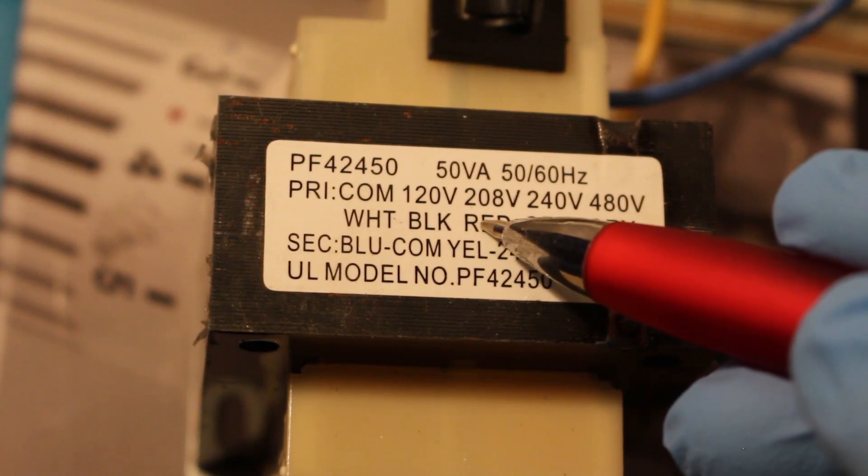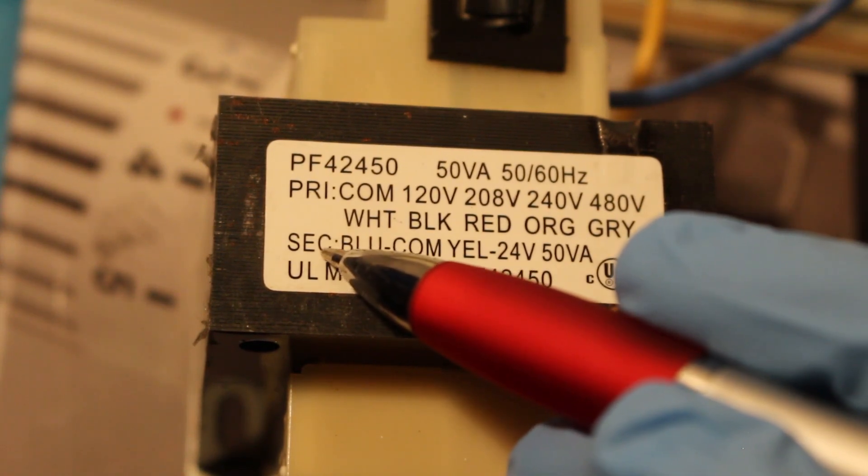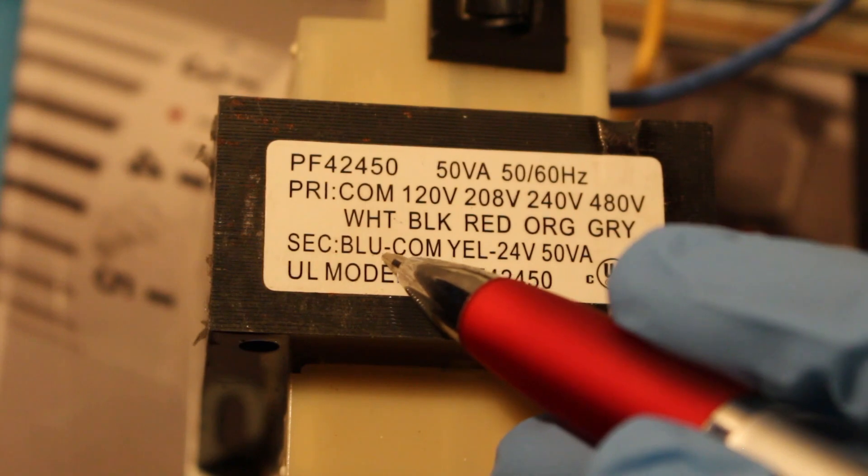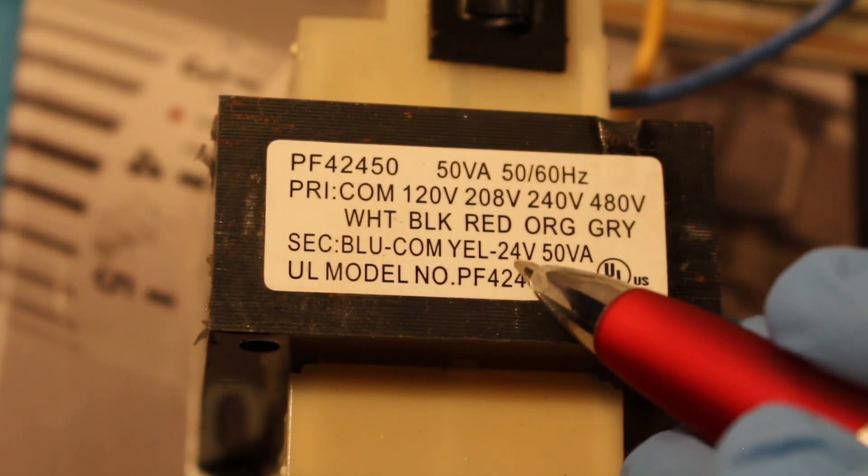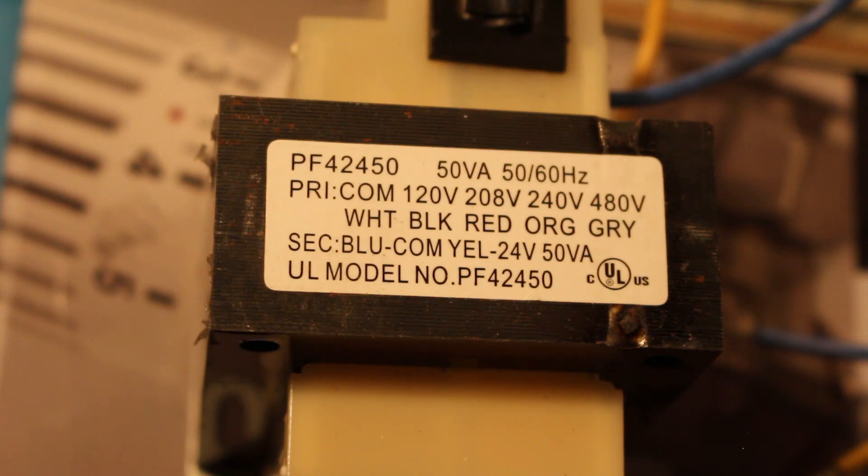So you would connect your white and red to your power source, and there's your incoming power for your primary coil. And automatically your secondary output will be 24 volts, which is the blue common wire and yellow which is your 24 volts. That is how you would wire this and this is how it works.